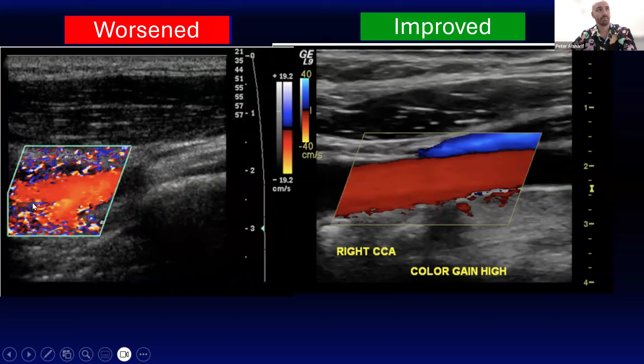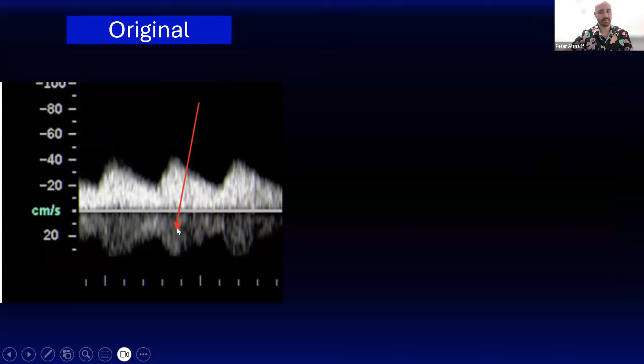Okay. Here we're doing some pulse wave Doppler, and we're getting this flow, which we expect in the positive direction, but then you're getting this kind of mirrored thing. And that looks weird. And I don't know that there's flow happening in both directions at the same time. That doesn't really make a lot of sense. And so what's happening here is a phenomenon called spectral mirroring. And so all you do to fix this is reduce the gain while you're shooting out pulse wave Doppler or continuous wave Doppler. And so what's happening is the machine is not picking up this artifact anymore.